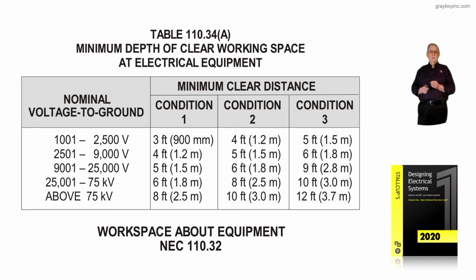You must be aware of this because we, as electricians and designing engineers, do a lot of design work and installation work above 1,000 volts up to 25,000 volts. Maintenance electricians perform a lot of maintenance on these systems, and we recommend Annex K and Annex L be reviewed very carefully for maintenance electricians because it does address frequency checks, good housekeeping, and other items of maintenance that are very important that the maintenance electrician knows. So this figure illustrates workspace about equipment over 1,000 volts in rating in accordance with NEC 110.32.